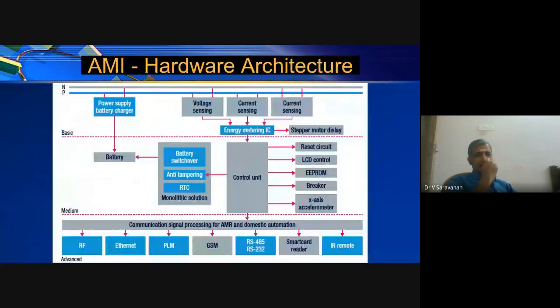This is a typical hardware architecture of an AMI meter. The top layer is the measurement and sensing layer, with a battery power supply for the meter, voltage sensing, and current sensing. This is further processed with the energy metering IC to convert it into an energy meter reading. There may be a stepper motor as well as a display system - the motor may be used to trip the breaker. The middle layer handles battery switchover when the power supply fails, and there is an anti-tampering system.